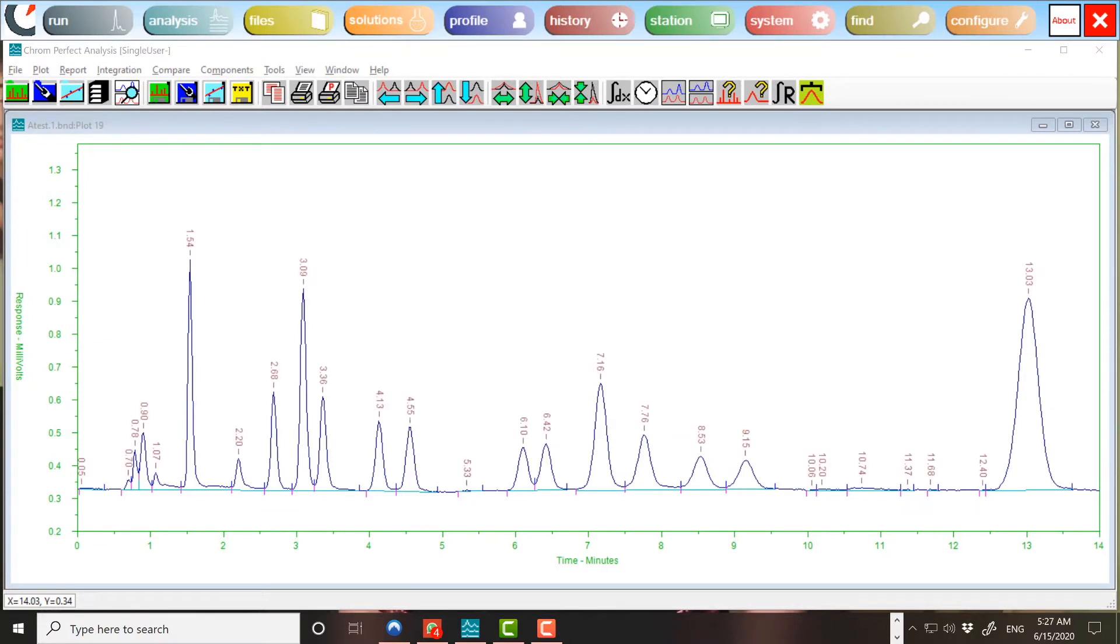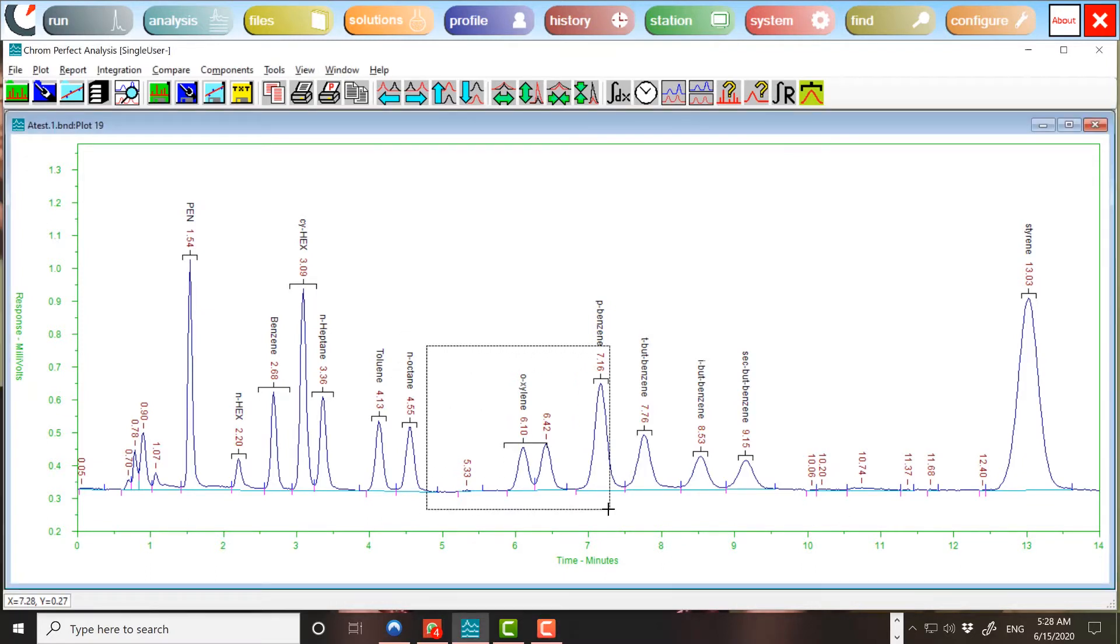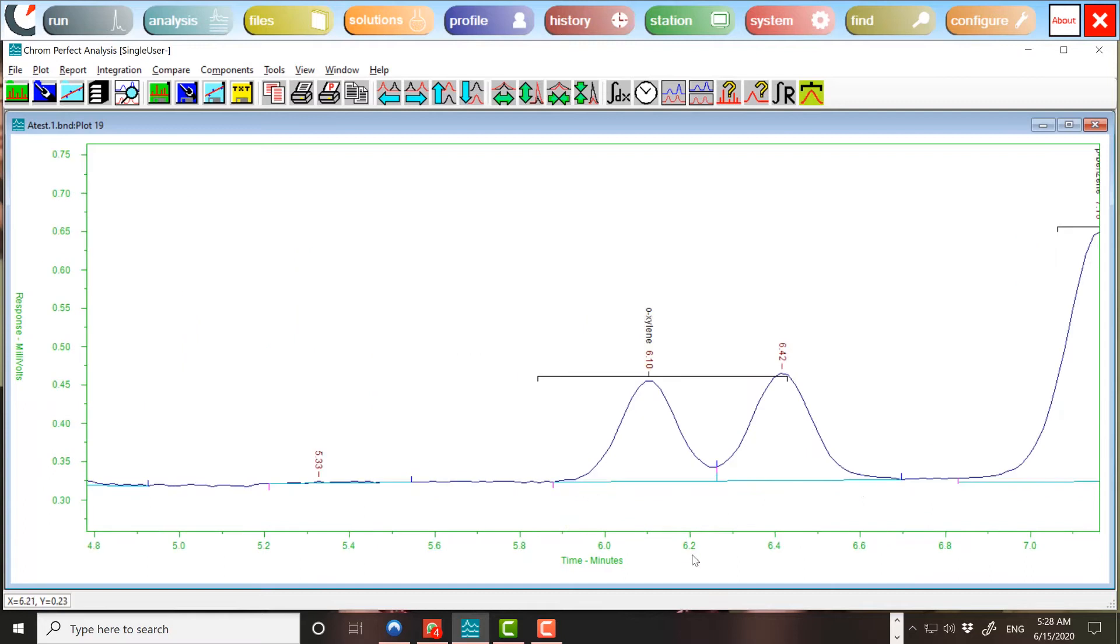Together, these determine the position and size of the search window for that component. If one or more peaks lie within the search window, then the peak that is closest to the center of the window, not necessarily the largest peak, is identified as the component.